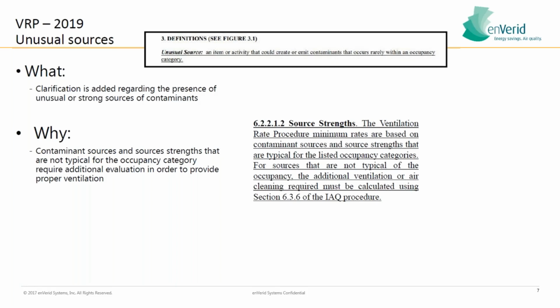And there was also some lack of clarity around which was the quote unquote safest methodology to use within ASHRAE 62.1. And what's interesting is that many engineers defaulted to the ventilation rate procedure, sometimes using demand control ventilation, and very rarely use the indoor air quality procedure. Now, with a lot of the new devices on the market, like enVerid, we're able to address the full list of contaminants. We have ASHRAE 145.2 testing for efficiency on those contaminants published.